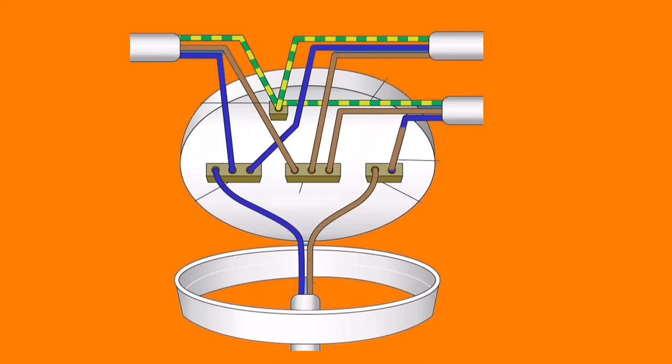The far left hand side has a block of three, which is identified with an N and that's for neutral within the ceiling rose itself. The centre block of three is identified with the word loop and has the permanent line connections coming in and out of it.